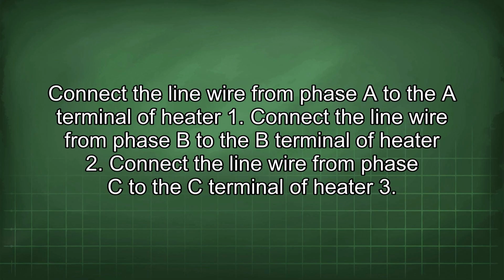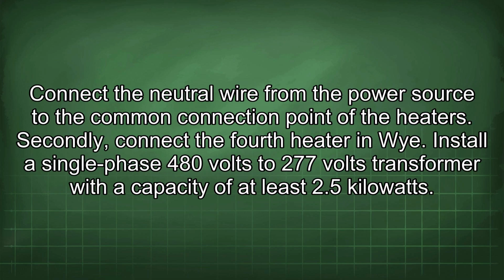Connect the line wire from phase A to the A terminal of heater. 1. Connect the line wire from phase B to the B terminal of heater. 2. Connect the line wire from phase C to the C terminal of heater. 3. Connect the neutral wire from the power source to the common connection point of the heaters.